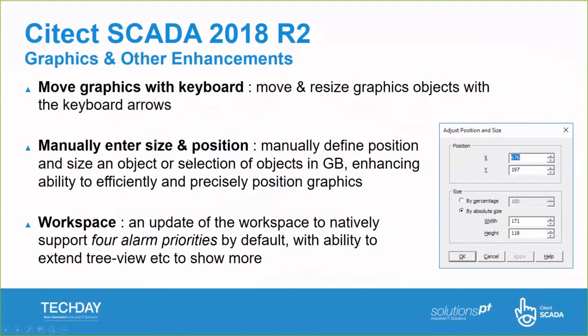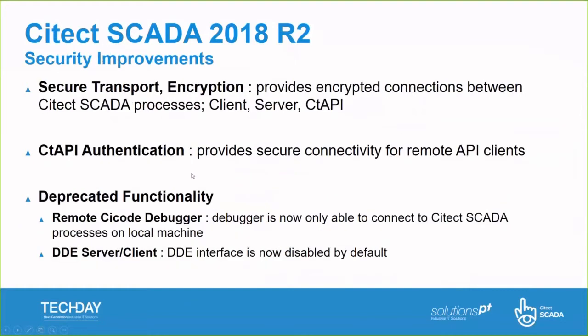Additional features include the ability to move graphics with keyboard arrow keys — something that has been requested for a while — as well as being able to manually enter the size and position of graphics, helping you to precisely position graphic symbols. Security improvements have been made in the R2 release: communication between server and client is now encrypted, CT API authentication provides much more secure connectivity for remote clients, and some functionality has been deprecated in order to make CITECT more secure.